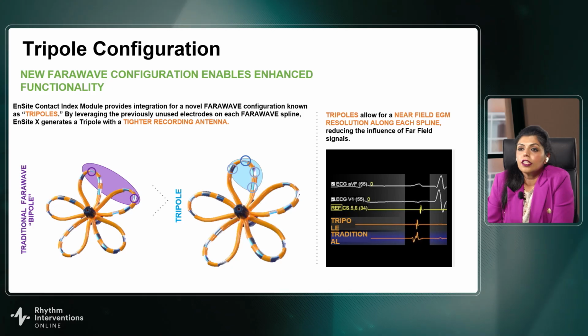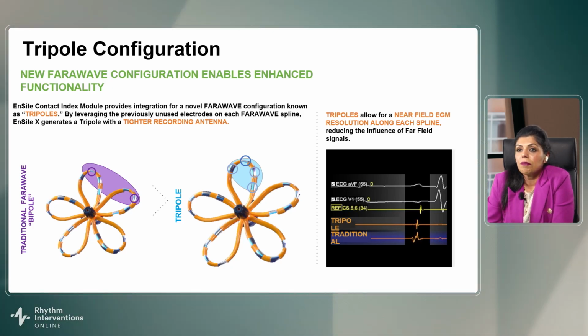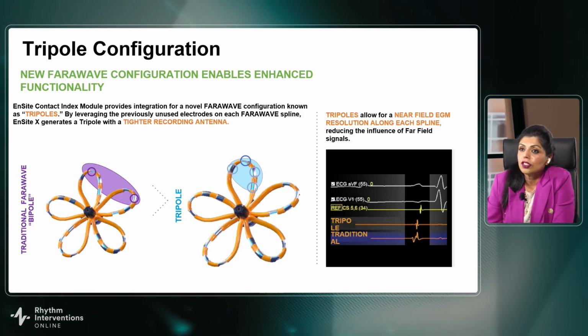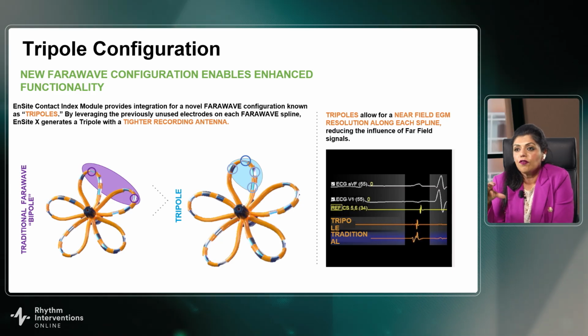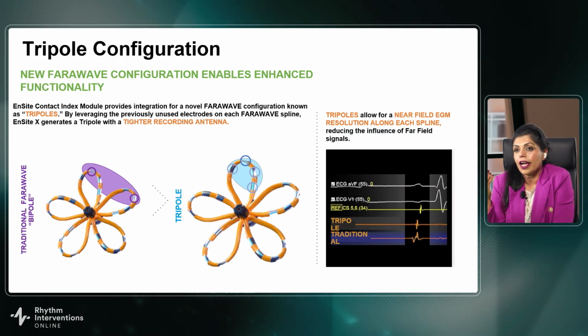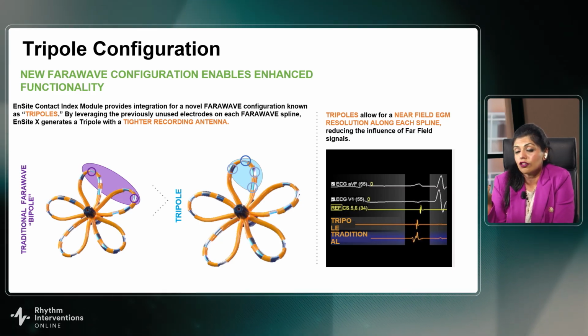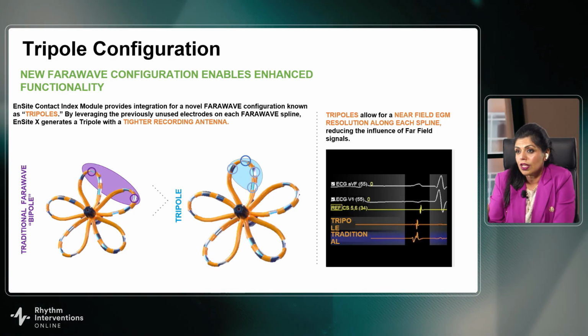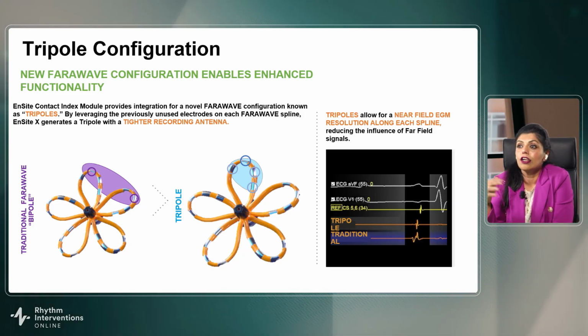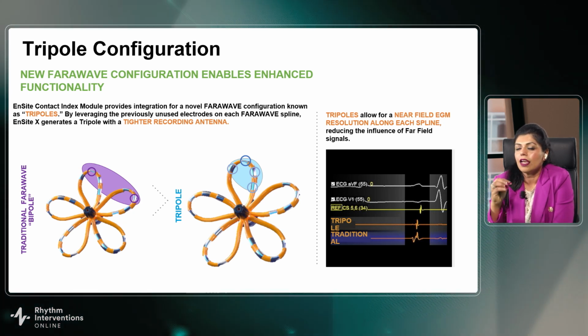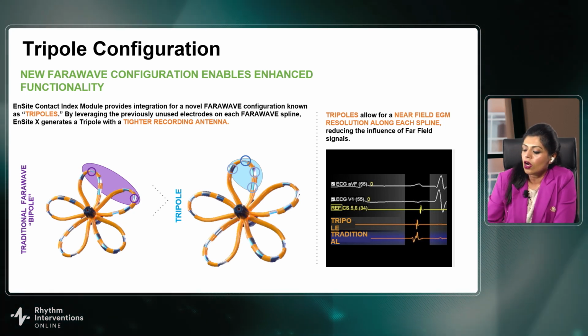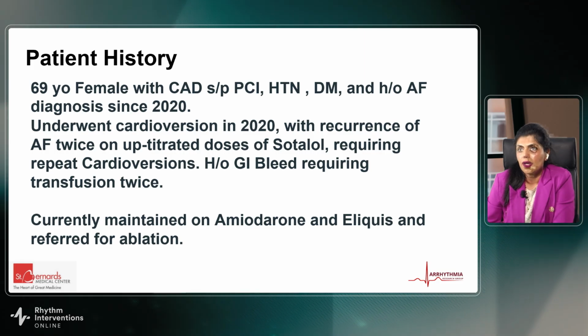One of the other configurations that you have with this new mapping solution is the tripole configuration. As you all know, with the FARAWAVE system, you're just looking at one of the electrodes. But now with the tripole configuration, you can see at least most of those electrodes. So it gives you a little better near-field EGM resolution along each spline, and lets you understand what the near-field and far-field signals are in a little better way.